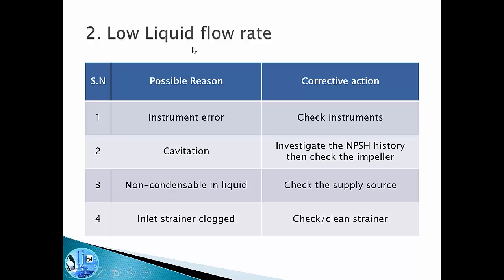The second problem is low liquid flow rate. The reasons could be an instrument error — we need to check if our instruments are giving correct readings. It could be cavitation of the casing or impeller, so we need to investigate the suction pressure history and check the impeller mechanically. It could be non-condensables in the liquid — we should check if any supply line feeding the common suction line is introducing gases, as this will affect pump flow. It could also be a clogged inlet strainer — we need to clean the strainer and restart the pump.